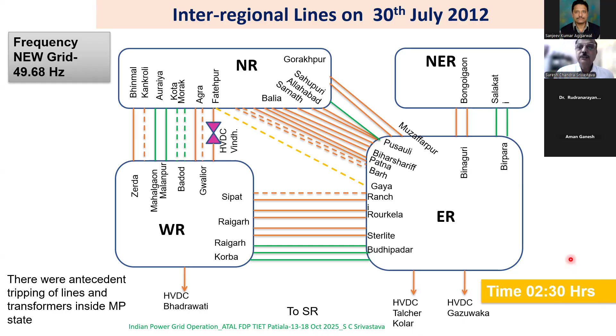Then oscillations were initiated. They were coupled together, and oscillations were seen between northern and the rest of the 3 regions. At that time, south was not synchronized. Because of oscillations, these lines tripped one by one, and finally all the lines were out and northern underwent blackout. A lot of indiscipline was there. The load shedding was bypassed. The governor was also bypassed, so they did not come to the rescue. So northern was under blackout. This was late at night, and it took almost 14 hours to recover it.